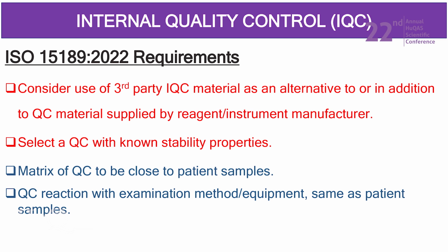And so that is something that we really recommend. Now, select an IQC with defined stability conditions. In most of the inserts of our IQCs, you'll find out that they indicate that this IQC material is stable for 7 days when kept at these temperature conditions. It is stable for this number of months when kept to these other conditions.